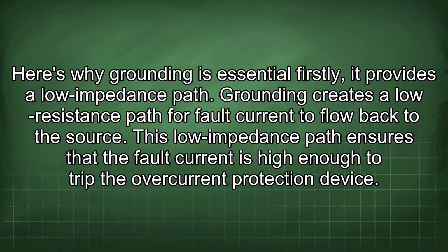Why is grounding essential? Firstly, it provides a low impedance path. Grounding creates a low resistance path for fault current to flow back to the source. This low impedance path ensures that the fault current is high enough to trip the overcurrent protection device.